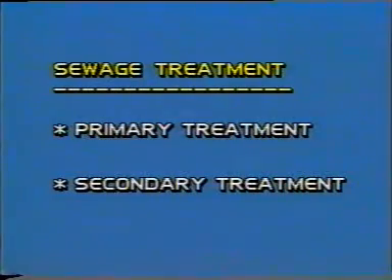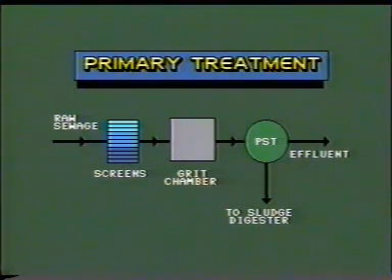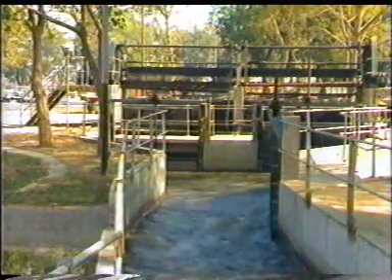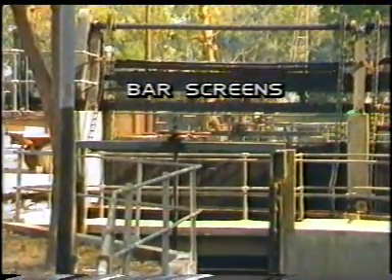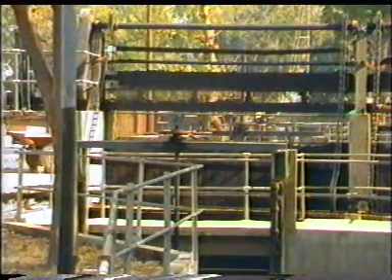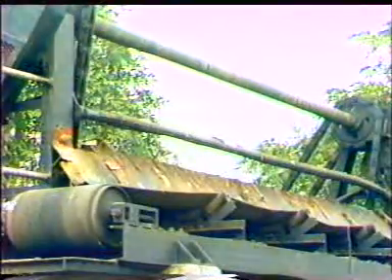Sewage treatment is carried out in two stages: primary treatment and secondary treatment. In primary treatment, sewage passes through bar screens, grit chamber, and primary settling tank. Sewage first passes through the bar screens, where floating and suspended matter such as wood, paper, and rags are removed. The waste material retained on bar screens may be lifted and removed mechanically with the help of a conveyor belt arrangement.